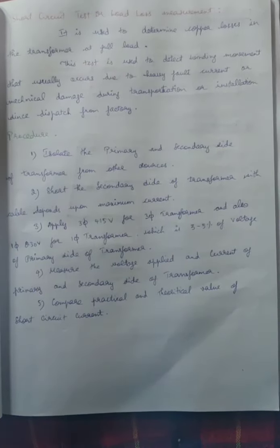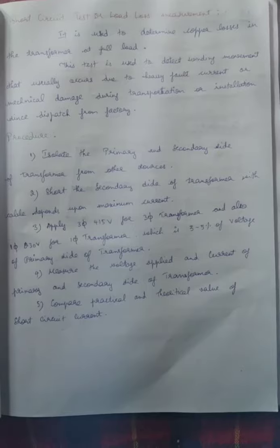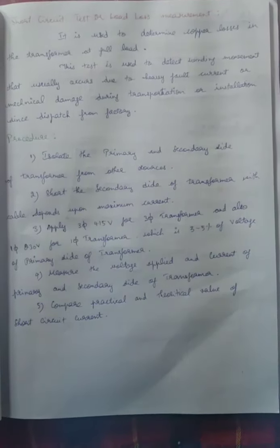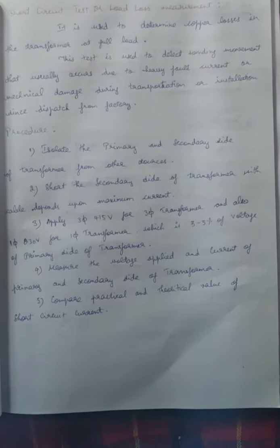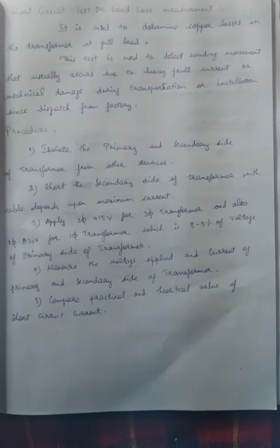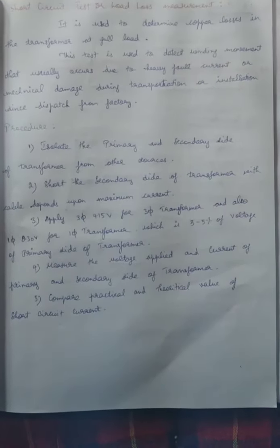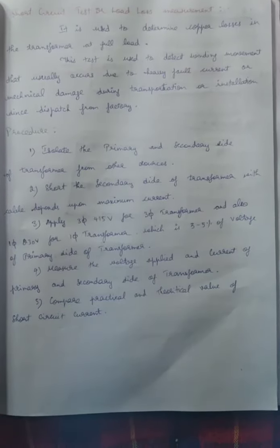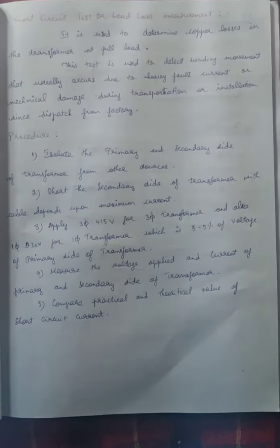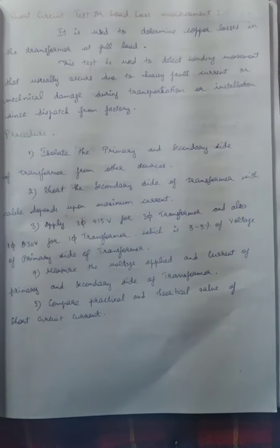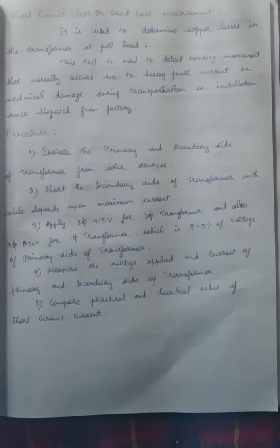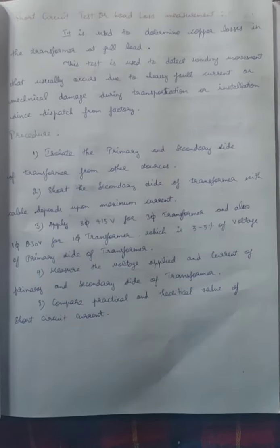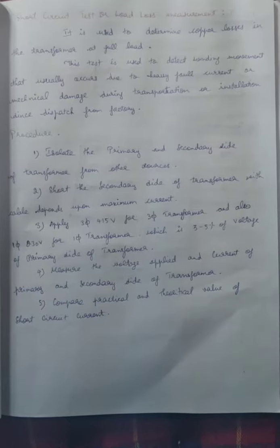Because on the primary side we have turns, which means tap changes. So the short circuit testing should be carried out for taps from the lowest tap to the maximum tap. It depends upon the customer's requirements. If we need to take only 3 to 4 tappings, which means at the start of the tapping, the nominal tap, and then the end of the tapping, mostly the customer will request these 3 areas of tappings for short circuit currents. So we need to measure them.